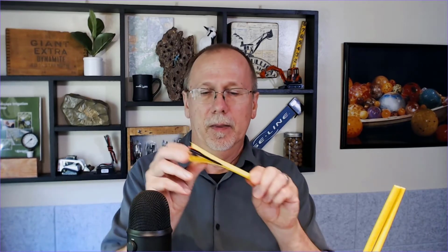Andy had talked about getting calls from folks with overcurrents or splice issues, definitely sounding like wire issues, and one of the questions asked is, did it rain? Are the valve boxes full of water? Well, what can happen is if you use that utility knife and nick down to the wire at this initial portion, and that valve box is full of water, that nick is now submerged underwater, as you can see in my glass of water, creating an overcurrent, or at least a splice issue. Those are things you want to avoid.